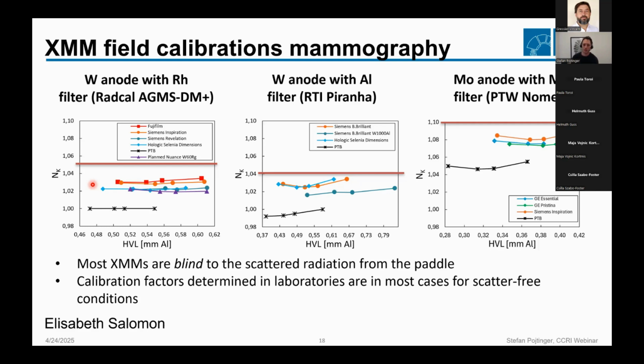Under laboratory conditions, of course, we calibrate without scatter, because if you want to establish a reference radiation field, which phantom are you going to use? So there's no standard for that, and we think that's a lot of where the difference is coming from between the laboratory calibration factors and the clinical calibration factors.